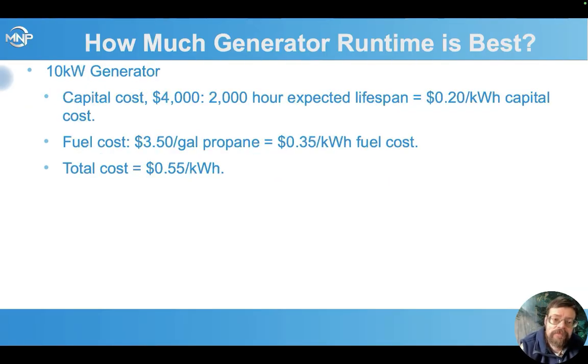How about the cost of the generator? Here we're looking at a kind of medium range standby air-cooled backup generator. Capital cost, and assuming a 2,000 hour expected lifespan, about 20 cents per kilowatt hour for the capital cost amortized over the life of the generator. That's already pretty high there. Fuel cost, assuming propane here, we're another 35 cents per kilowatt hour for fuel costs. So our total cost to run that generator for a kilowatt hour is 55 cents per kilowatt hour. That's pretty high. That's a lot higher than typical grid power is, and a lot higher than a lot of our numbers we are looking at for solar.